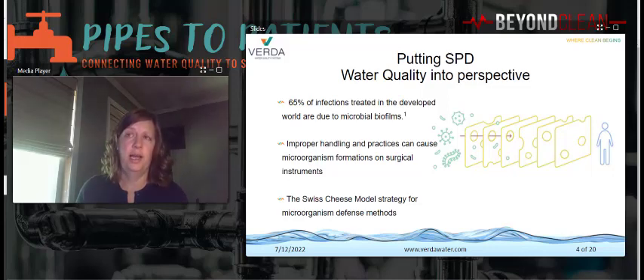impact on patient care. While high quality water by itself will not guarantee contamination-free instruments, it's one of many critical defense methods used when reprocessing instruments. Healthcare facilities employ multiple techniques, each a defense method against microorganism growth. Each defense method has holes and exceptions through which errors and mistakes can pass, so individually each one is flawed. Imagine a flawed method is like a slice of Swiss cheese, with the holes representing the flaws, allowing microorganism formation on instruments. If you put enough flawed Swiss cheese slices together, the holes don't line up and errors, that is microorganism growth on instruments, can't reach the patient.